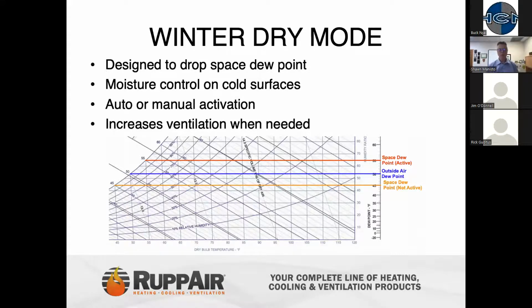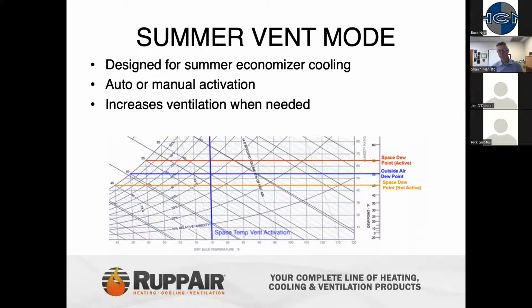Beyond the winter dry mode capability, also having a system in place that can also be a summer vent mode, basically recognizing kind of the same conditions, but we have an activation point here where we look at space temperature, where we're too warm in the space. We can start activating different configurations saying, right now, today, this summer day is a dry, cool day. We want to utilize this for some free economizer cooling and automatically introducing that into the space as needed. So increasing ventilation rates when the best time of day stands.